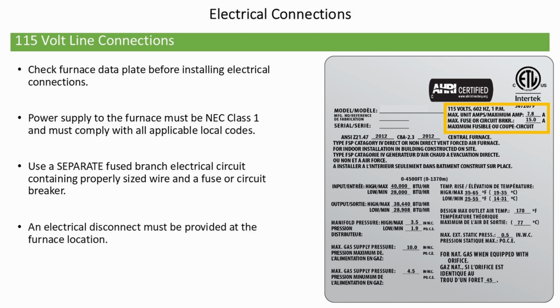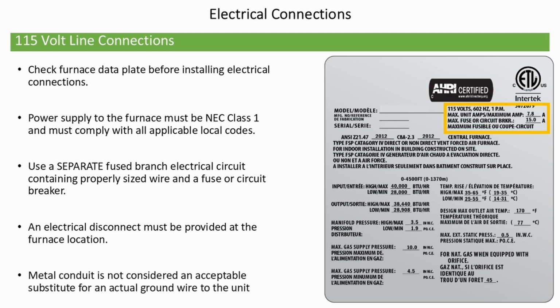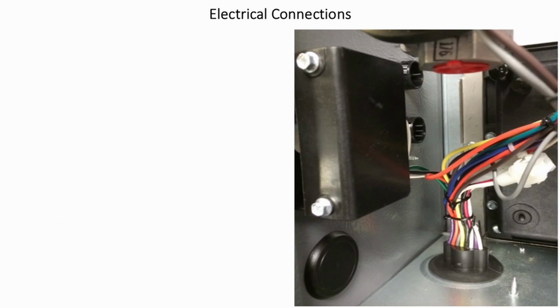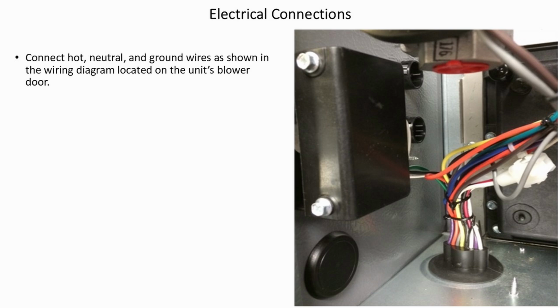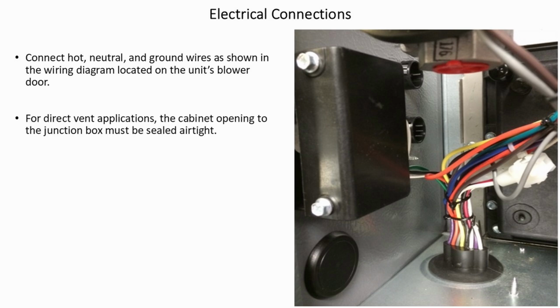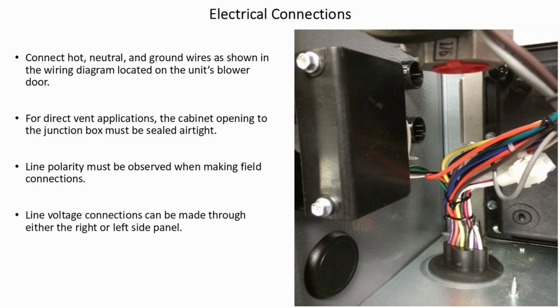An electrical disconnect must be provided at the furnace location. Metal conduit is not considered an acceptable substitute for an actual ground wire to the unit. Connect hot, neutral, and ground wires as shown in the wiring diagram located on the unit's blower door. For direct vent applications, the cabinet opening to the junction box must be sealed airtight. When making field power connections, it's important to get the polarity correct. Line voltage connections can be made through either the right side or left side panel.